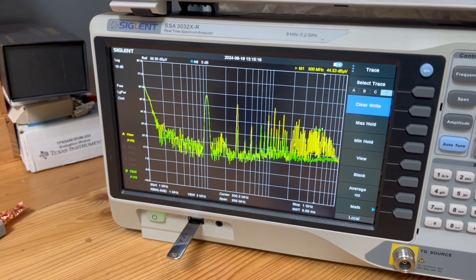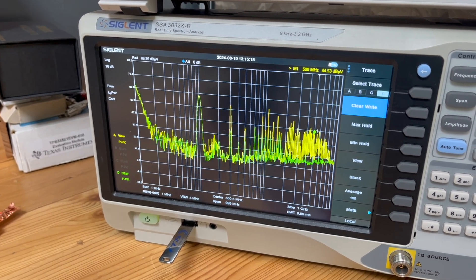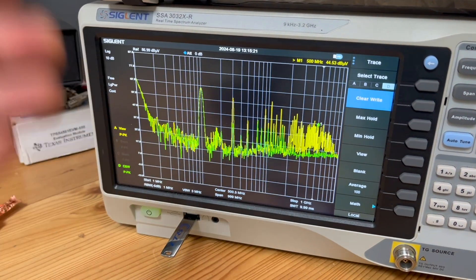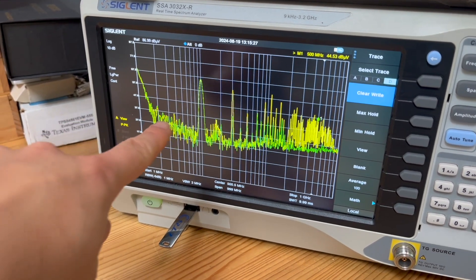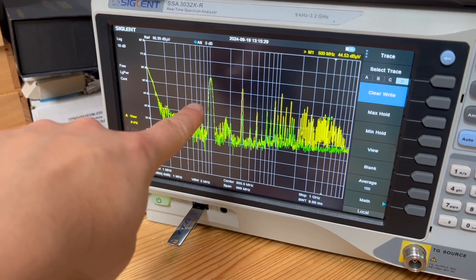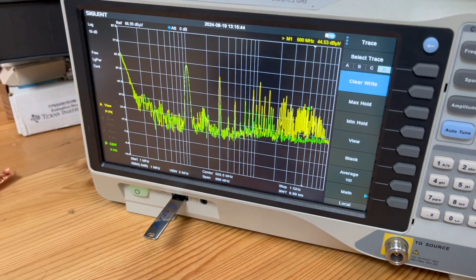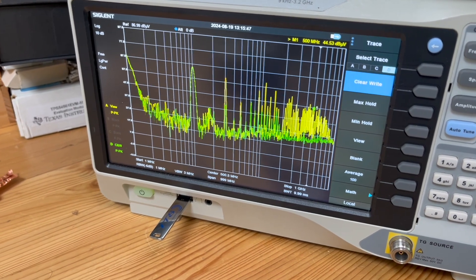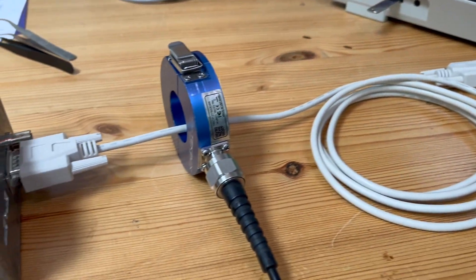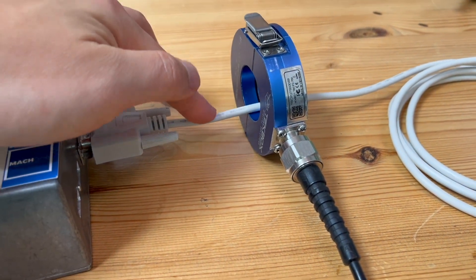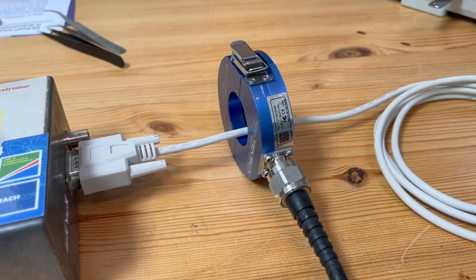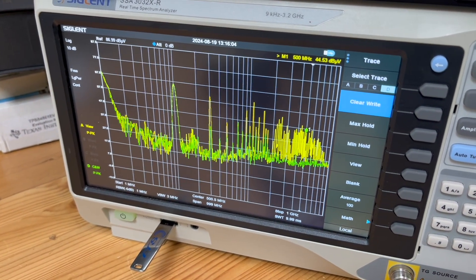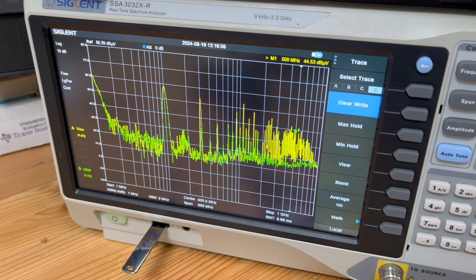Well, it does make sense because this particular seal has a small capacitor of picofarads range. So tens of picofarads, so yeah, it's very effective in a higher frequency range. Not so much at the lower frequency range as you can see. Particularly as we demonstrated, this low frequency noise can be suppressed if the drain wire is connected properly, but in this case it is not. So I suspect this cable might have the drain wire not terminated well. But yeah, in terms of the high frequency performance, it's really good from the frequency domain analysis.